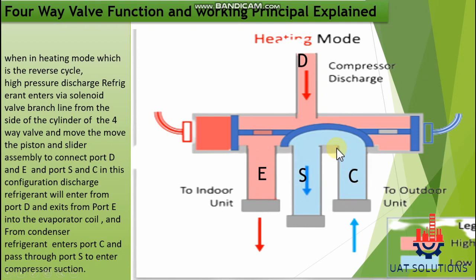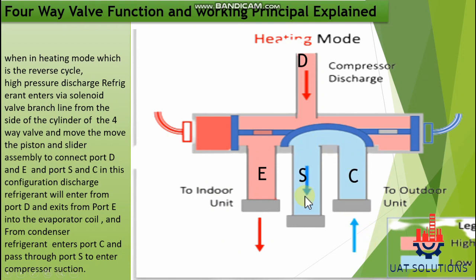In this configuration, discharge refrigerant will enter from port D and exit from port E into the evaporator coil, and from the condenser, refrigerant enters port C and passes through port S to enter the compressor suction.